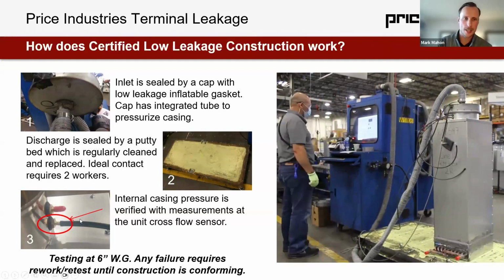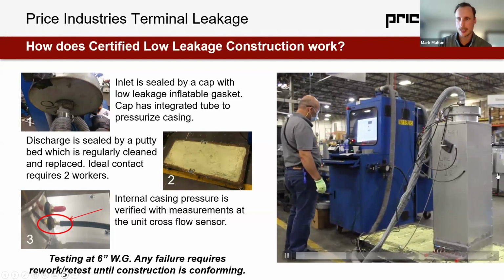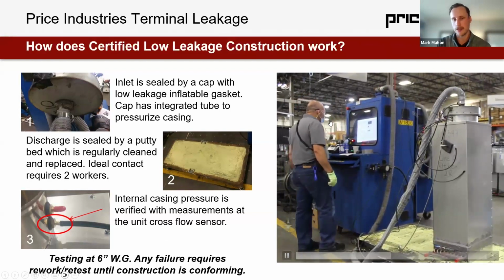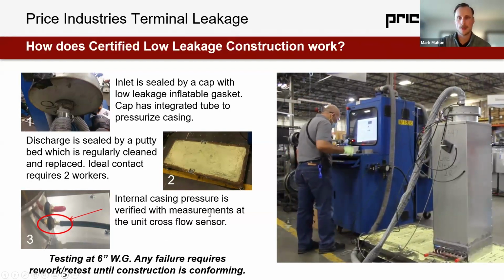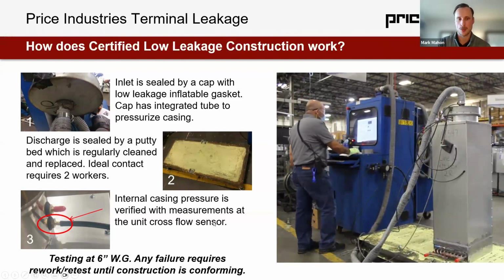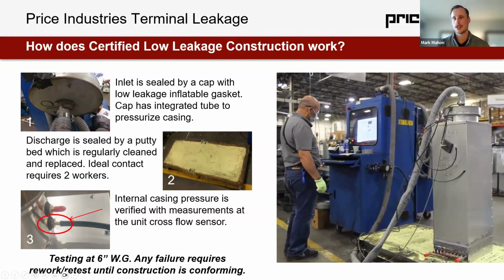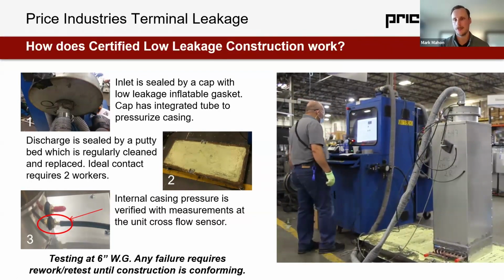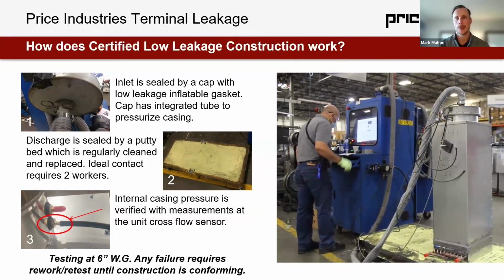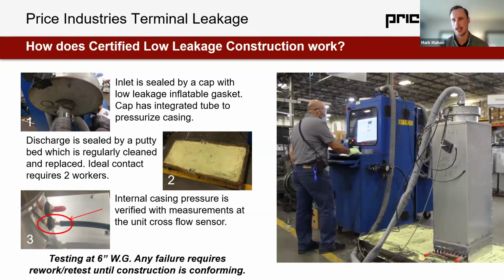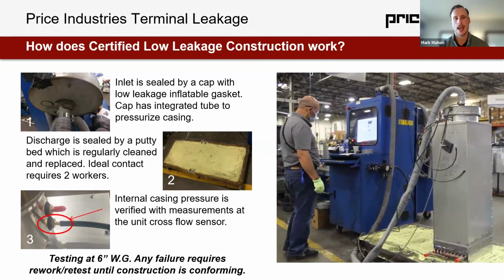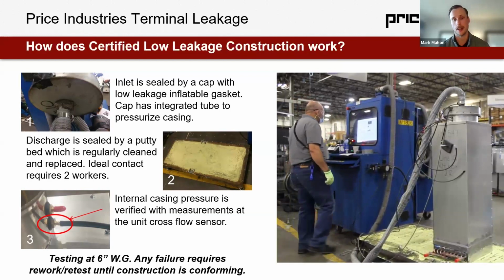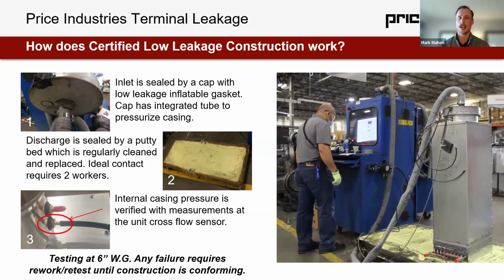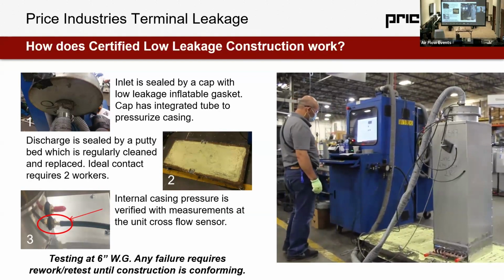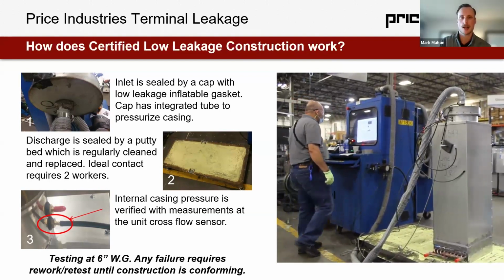We then pressurize the casing. We measure the internal pressure of the casing through the static pressure side of our cross-flow sensor. At the factory, we test to 6 inches water gauge. Essentially every single box would be pulled off the end of the line and taken to this rig. A test occurs, and it usually takes maybe 10 minutes. The big issue is that if there is a failure, it's going to require rework and then retest until construction is conforming. That speaks to the expense of certified low leakage construction.